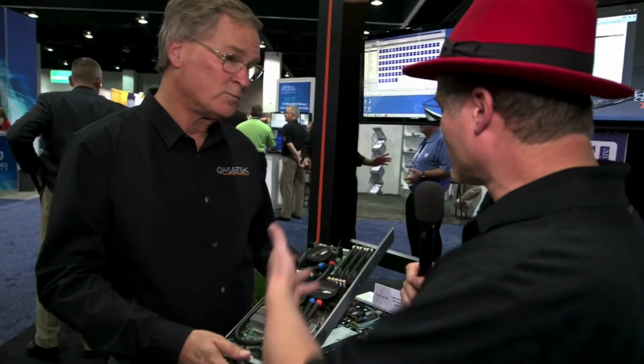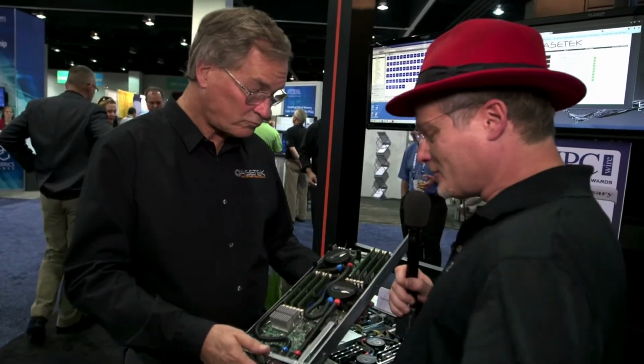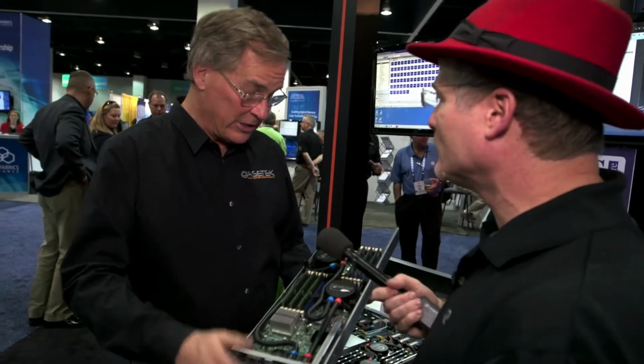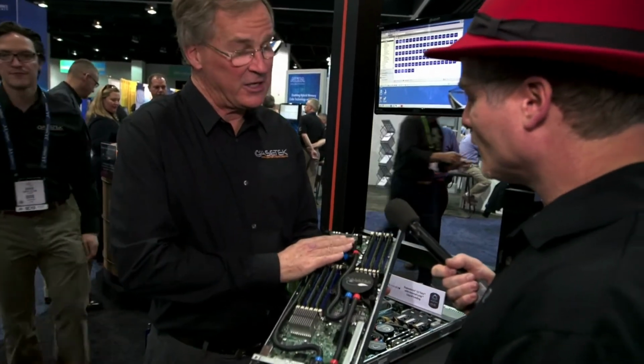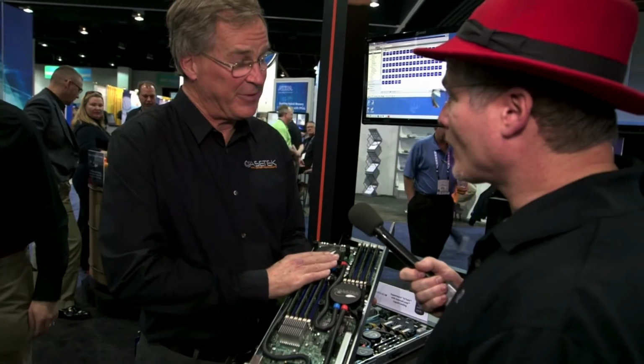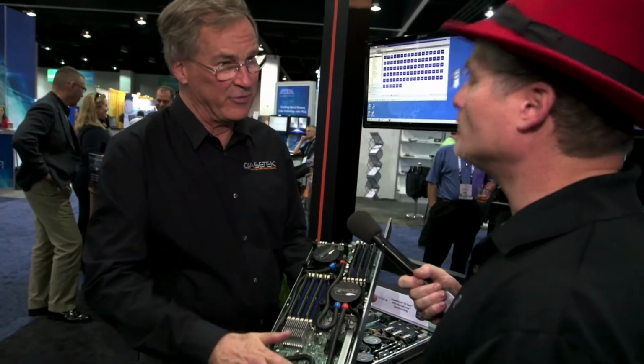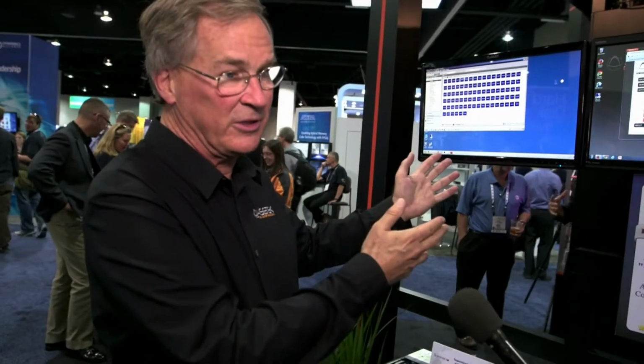Okay, and then you basically don't need fans to blow air constantly, do you? Now we still use fans because we're taking the GPU or CPU heat out, but we're still cooling memory and other popcorn parts with fans. So that's why I say that in this unit, which is 36 kilowatts, we're actually cooling 20 kilowatts with liquid.